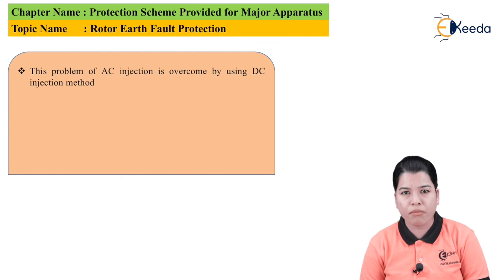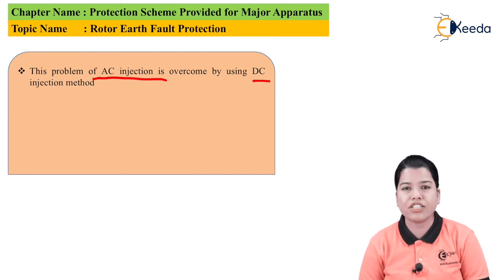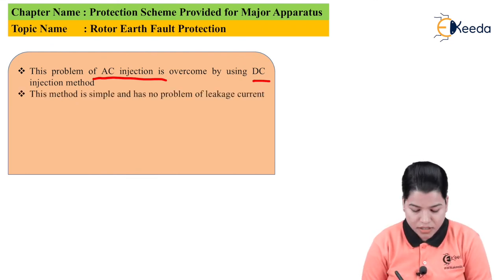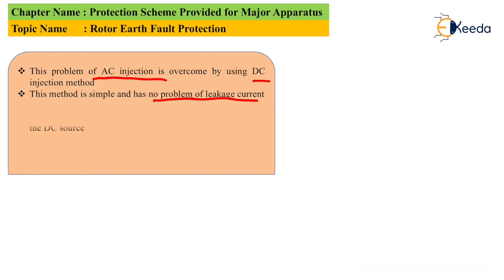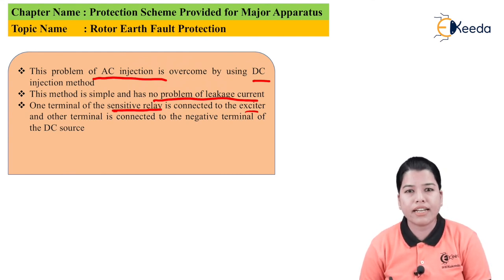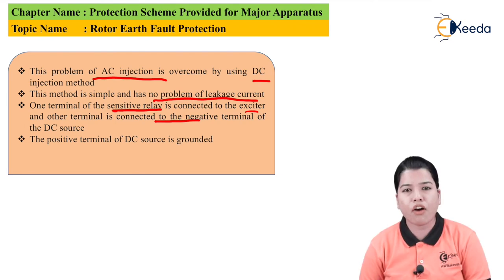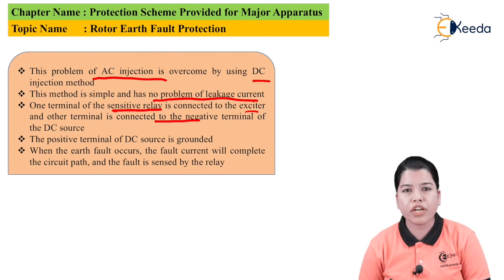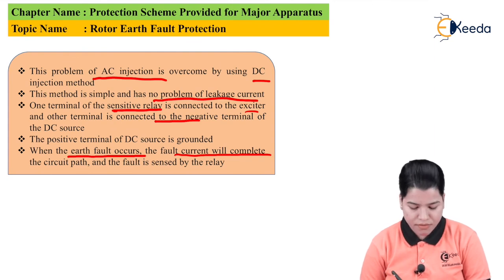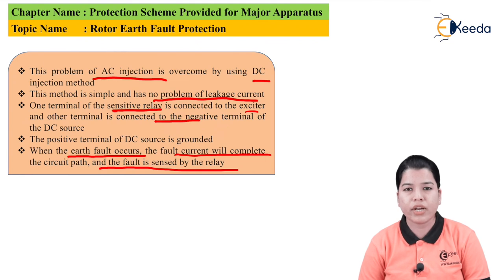The problem of AC injection can be overcome by using the DC injection method — that is, instead of AC current, we inject DC. This method is very simple and has no problem of leakage current. One terminal of the sensitive relay is connected to the exciter and the other terminal is connected to the negative terminal of the DC source, while the positive terminal of the DC source is grounded. Whenever an earth fault occurs, the fault current will complete its circuit path and the fault will be sensed by the relay. In this way, using these two methods, we can protect the rotor from earth fault.